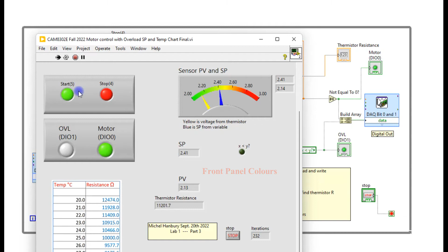The green one is pulled low; when I press it, it goes to +5. So my motor is turning on because my set point is higher than my thermistor temperature. I'm going to drop this a little bit. Okay, and then increase the temperature, it goes up, turns off my overload, and even if I try to start it here, the motor never comes on.